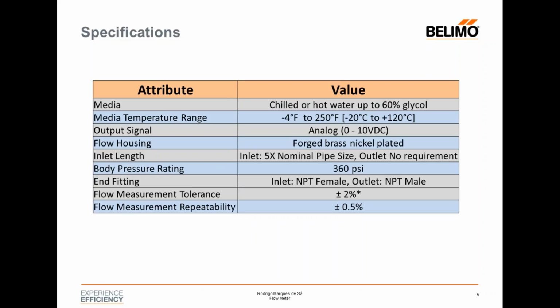This is a good point, the inlet length. We have to respect this: 5D, meaning 5 times the diameter, before the flow meter on the inlet side. For the outlet side, there's no requirement.